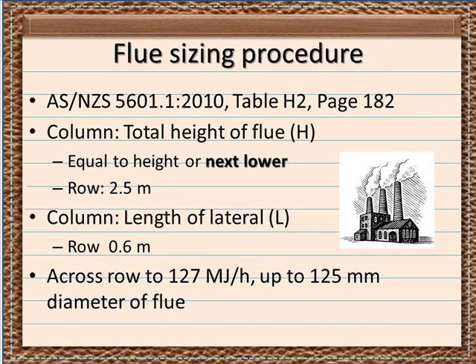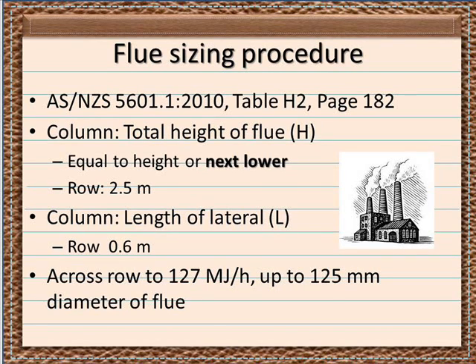We now go to Table H2, which is for low heat loss materials and indoor locations. Looking down the total height of the flue column, we go down to 3 metres. But step 2 says to go to the height equal to the flue height or the next lower flue height. Therefore, because this flue is 2.7 metres in height, we must go down to 2.5 metres. We go across to 0.6 metres and move across that row until it shows greater than 120 megajoules. We find the 127 megajoules figure, which is above the 120 megajoules requirement. Moving to the top of that column indicates that a 125 millimetre diameter flue is necessary.